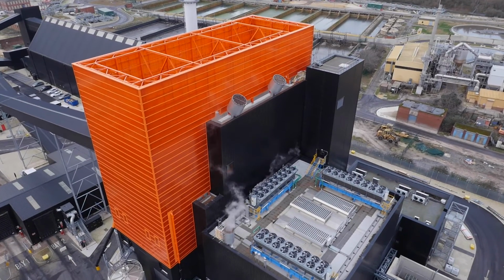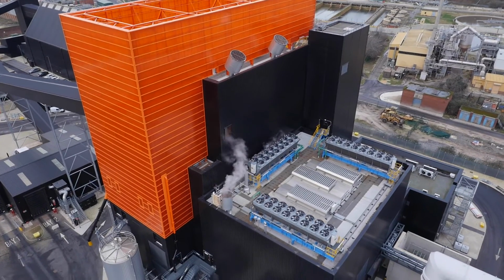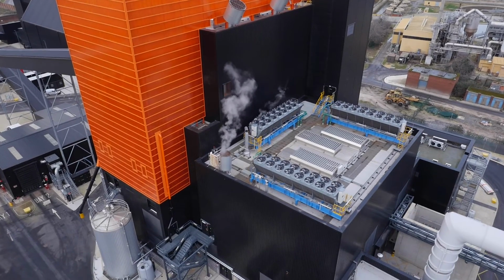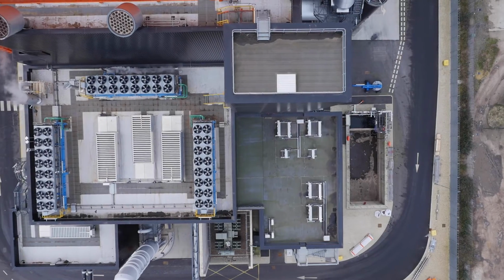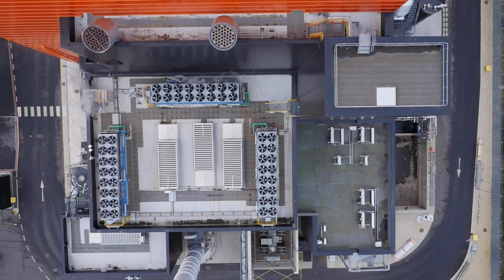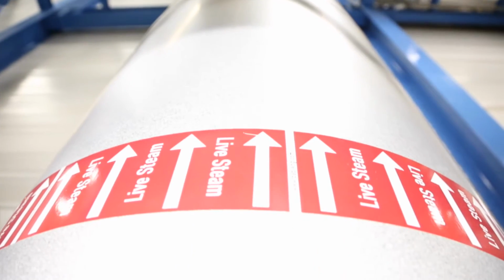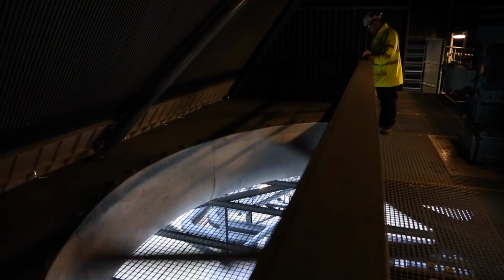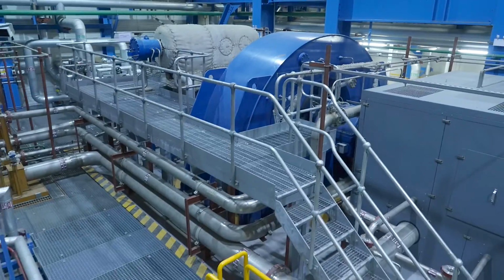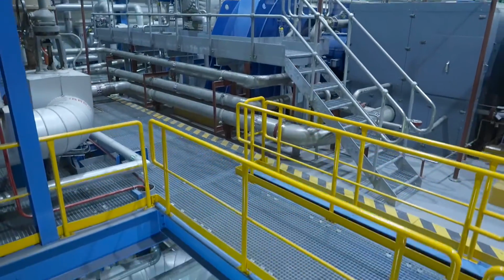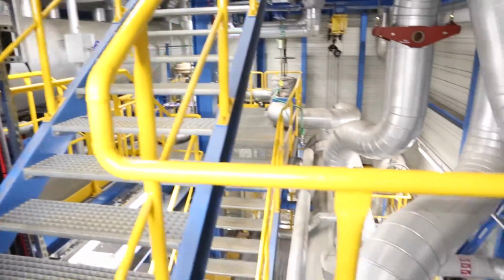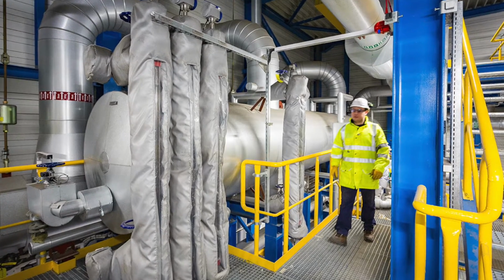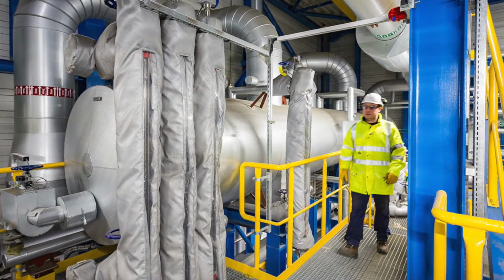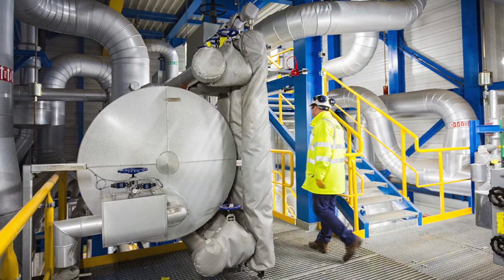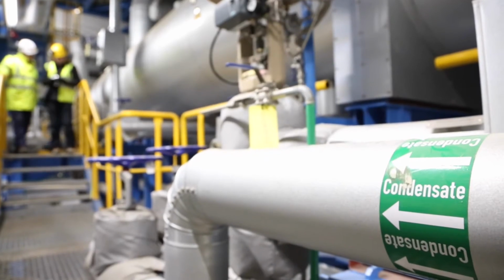After signature of the main contract in November 2011, the design of the district heating system was agreed and also became part of Andritz's scope of works. The steam is expanded in the steam turbine and is then condensed in an air-cooled condenser. A steam turbine bypass is installed for process setups and startup. The heat is extracted via 2 heat exchangers set at different pressure levels. In part load, the bleeds to the heat exchangers can be switched in order to adapt to the heat load requirements.